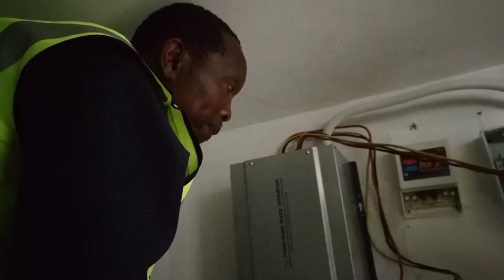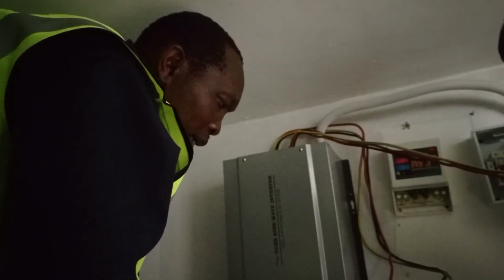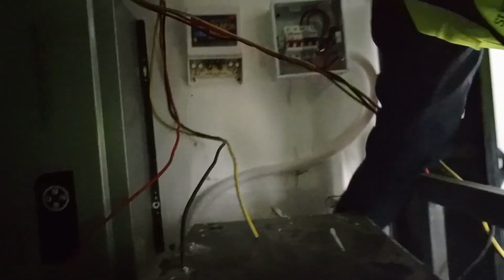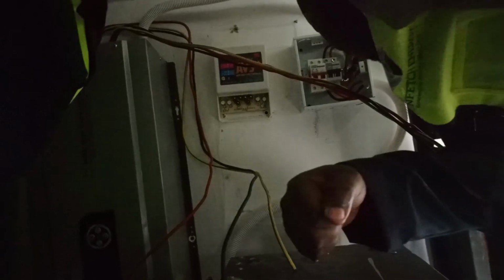After completing this unit, we use the same existing panel, then work on the power bank and our hybrid to recharge our new batteries. That's a good move. So for now, you want to remove it? I want to put off the system, since there is no isolator switch. Just remove directly from the battery. I'm going to disconnect the conversion unit, to avoid the smoke.